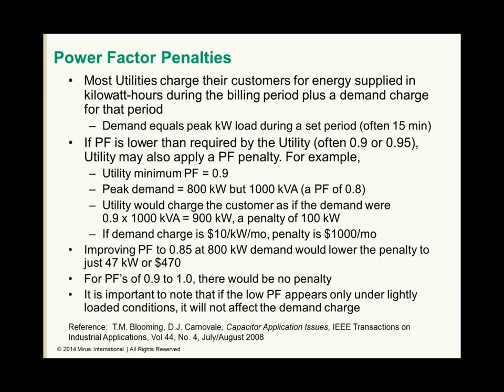An example of this would be if the minimum utility power factor was, say, 0.9, but the actual load at the facility was 800 kilowatts of real power and 1,000 kVA of apparent power, which would be a power factor of 0.8. The utility would charge the customer as if the demand were 0.9 times 1,000 kVA, or 900 kilowatts. So they take the apparent power value and multiply it by the minimum power factor they will allow. That would result in a penalty of 100 kilowatts in this case. If the demand charge was $10 per kilowatt, which can vary quite dramatically but is a fairly typical level, then that would be a penalty of $1,000 per month. So a fairly significant addition to a power bill.